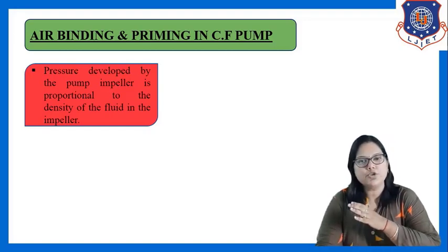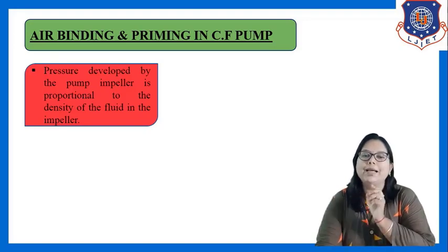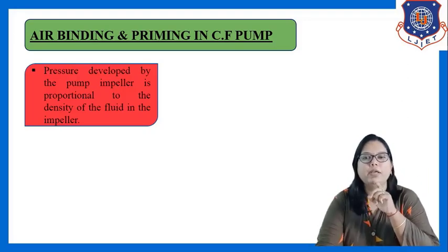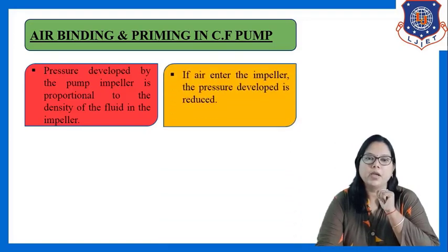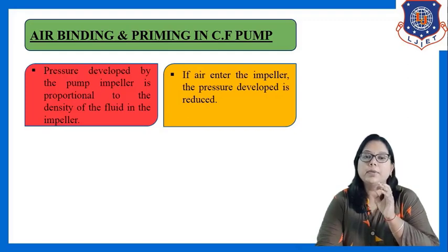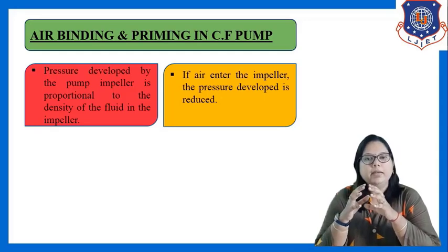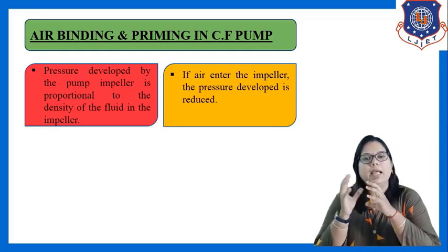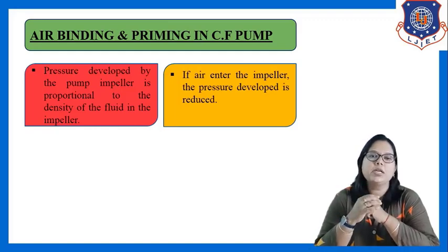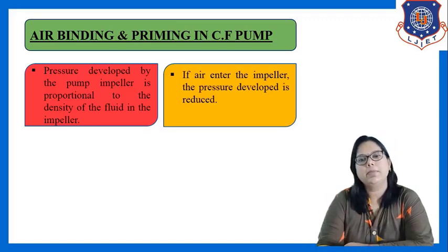This is the basic situation where the pressure developed by the pump impeller is proportional to the density of the fluid in the impeller. If air enters the impeller, pressure developed is reduced. When air enters the pump impeller, at that time pressure developed is reduced, and that is not a desirable situation.